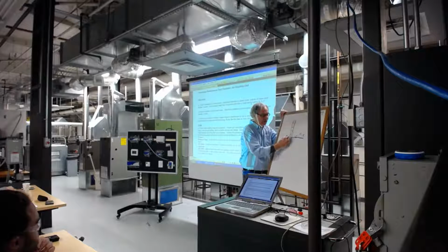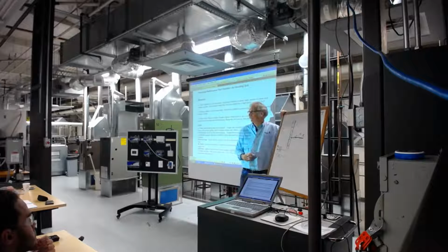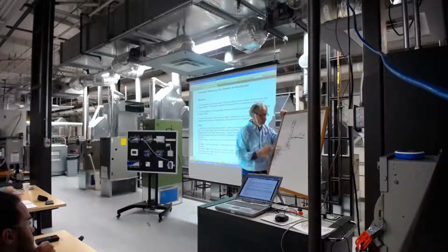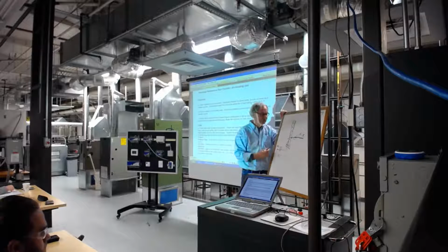As it begins to penetrate more and more, you begin to hit this surface. As you get closer to this surface, you're going to be at dew point. Well, hopefully. What happens when you're at dew point? You're going to condense. So there's your drip pan, and now you've got your condensate coming down. You lower the sensible, and you also do the dehumidification. So this is like your pre-cooling, and as you walk through it, you begin to approach the saturation line, which again is dew point, 100% humidity.